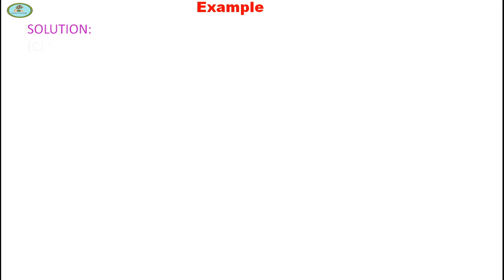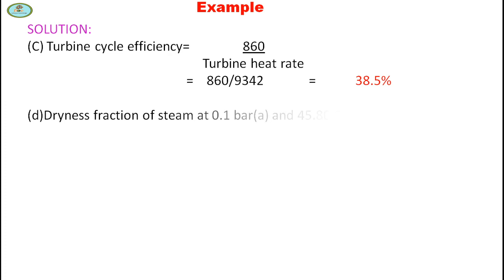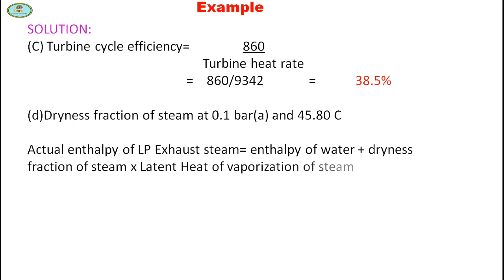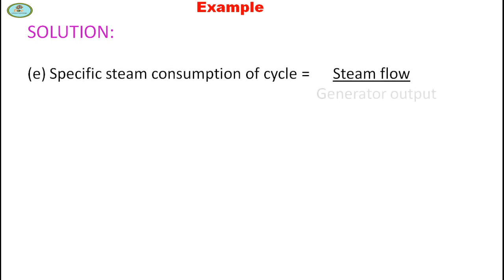Turbine cycle efficiency equals 860 divided by turbine heat rate = 860 / 9342 = 38.5%. For dryness fraction of steam at 0.1 bar and 45.80°C: actual enthalpy of LP exhaust steam = enthalpy of water + dryness fraction × latent heat of vaporization. Substituting: 2426 = 191.9 + x × (2584.9 − 191.9), giving dryness fraction of steam = 93.35%.